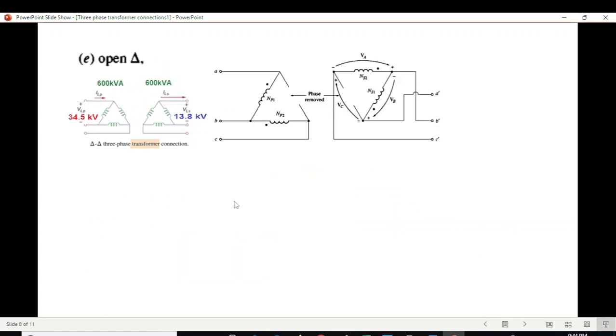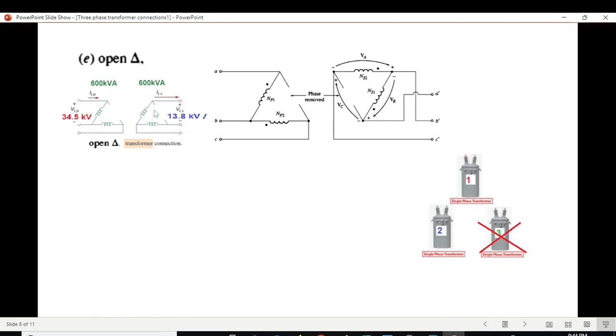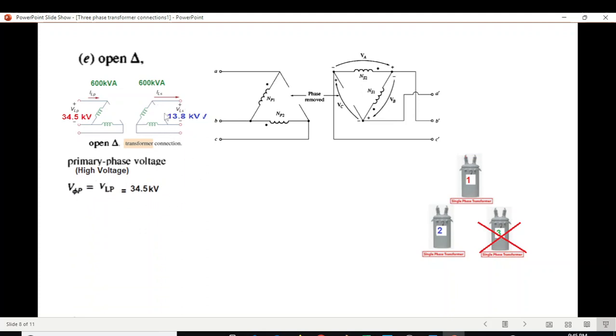Now we discuss open delta. In a normal delta circuit, if one of the three single-phase transformers fails or is removed, only two transformers remain — that is the open delta configuration. We remove the third transformer from the circuit. Since this is still a delta connection, the line voltage and phase voltage remain the same, so the primary phase voltage is 34.5 kV.